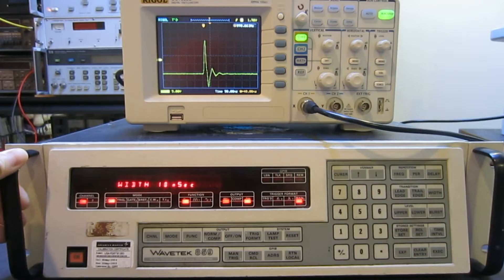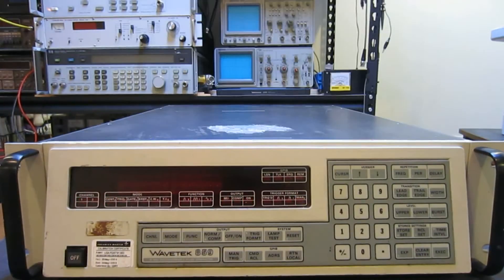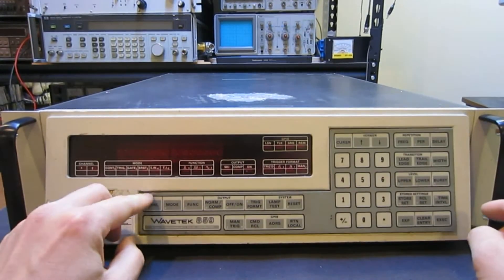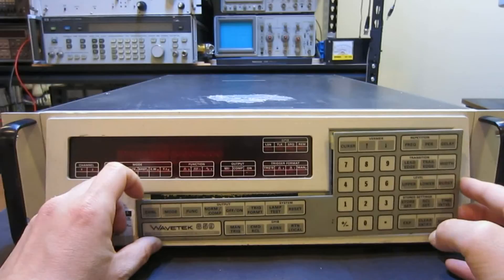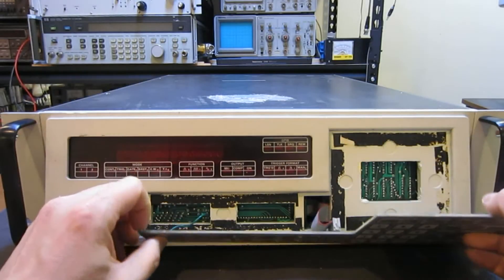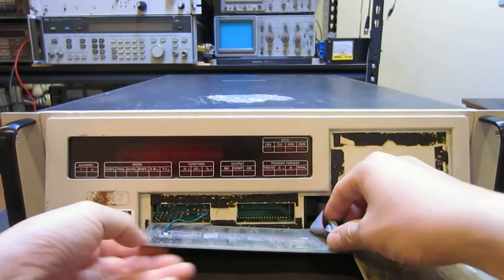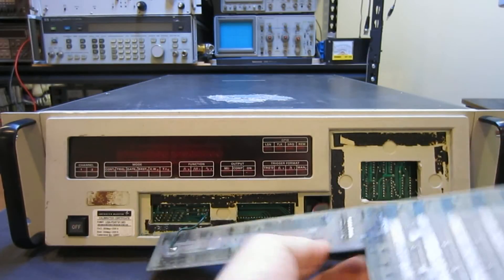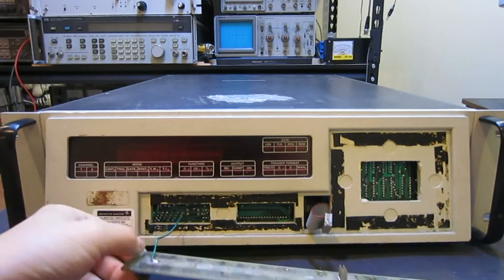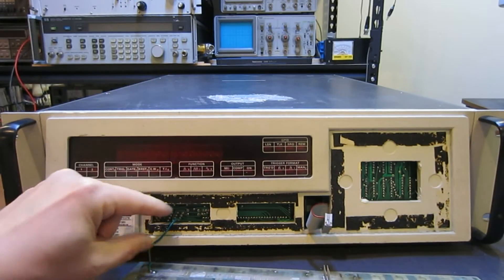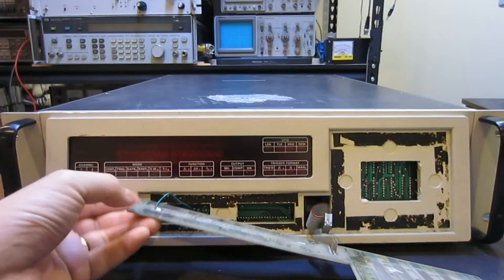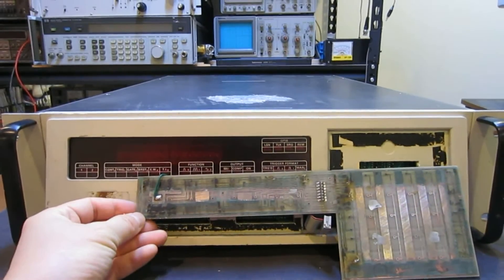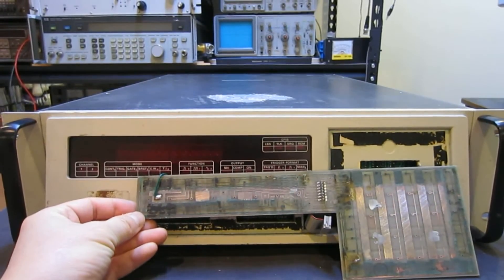Now let me show you what I have done in order to fix this unit. I'm going to turn off the power and remove this front panel. The panel I haven't glued back in place yet. Basically there's a connector connecting to this panel. I can disconnect it. Originally there's a wire here that's very short. I extended it. This is just the wire for the ground, for the earth ground.